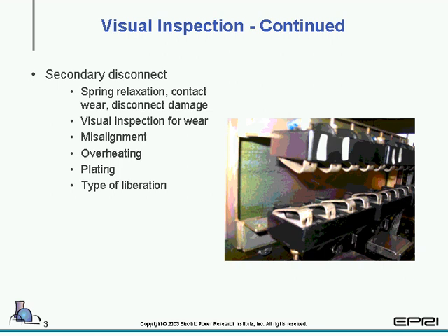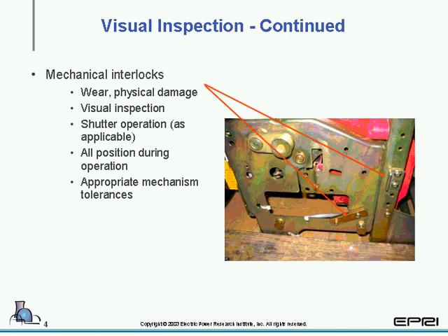Next one we're going to take a look at is secondary disconnects. We have a list. When you're looking at the secondary disconnects, it's important to also look at the secondary disconnects in the cubicle to see how they're made up. And next one we're going to take a look at is mechanical interlocks. Now there are many varieties of mechanical interlocks, so as well as the list, some interlocks may have to be tested by installing the breaker into the cubicle and cannot be tested directly on the breaker alone.